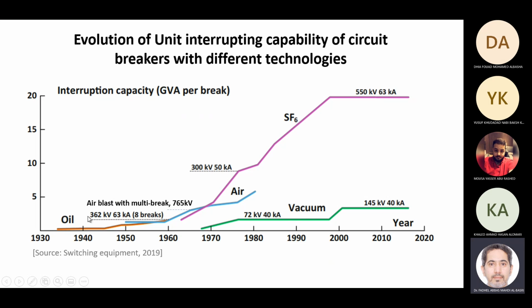So historically, from 1900, this shows you the historic development time in years versus its breaking capacity, its interrupting capacity, the maximum current that these breakers can handle. Initially, the breakers were designed based on oil as an insulation media, in roughly the 1930s. Then their breaking capacity is low.